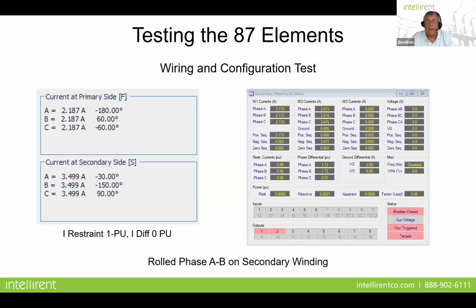Now, let's say I've rolled phase A and B on the secondary winding. Let's say that I just put my test leads on the wrong phases. What you're going to see here is we go from positive sequence to negative sequence values. So that would indicate that I've got the test set wired improperly. And also you're going to see the relay pickup. So you see that now these pickups are activated. I would say most definitely that this will cause your differential to trip. Because remember, the differential not only operates on the current values that it's seeing, but it's also looking at the phase angle as well. So if your relay is configured wrong or your wiring's wrong, that 87 is going to nuisance trip on you.